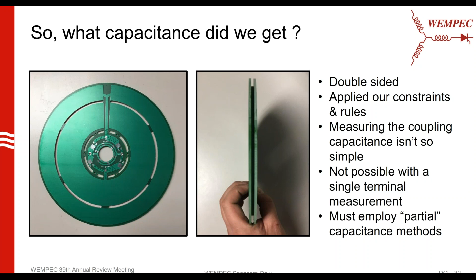To measure what we have, you have to use what's called a partial capacitance method. If you measure at the terminals, 1 and 3 on the stator and 2 and 4 on the rotor, those are the quote-unquote areas facing each other, but there are also all these other parasitic capacitances that exist.